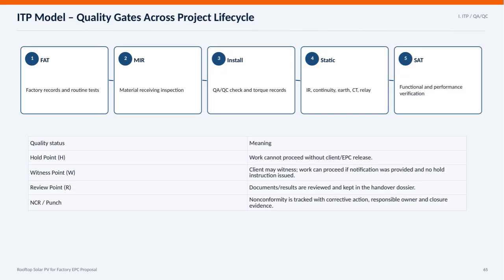Here we have the ITP model illustrating quality gates across the project lifecycle for our rooftop solar PV factory EPC proposal. The process is divided into 5 key stages. First is FAT, where factory records and routine tests are conducted. Next, MIR involves material receiving inspection to ensure everything meets standards. Then during the install phase, we perform QA/QC checks and record torque data to confirm proper assembly. Following that is the static stage, which includes essential electrical tests like IR, continuity, earth, CT, and relay verification. Finally, SAT focuses on functional and performance verification to ensure the system meets all operational requirements. These quality gates are critical checkpoints that help maintain high standards throughout the project.